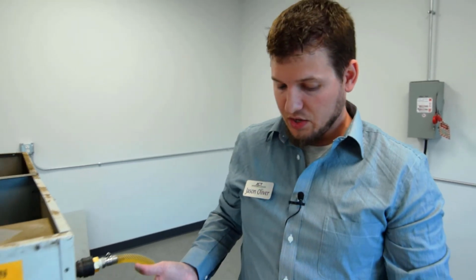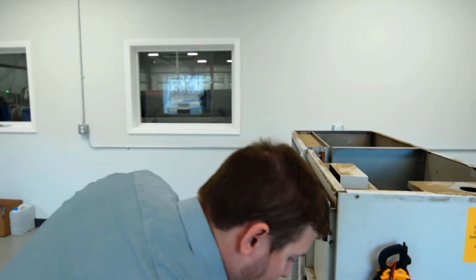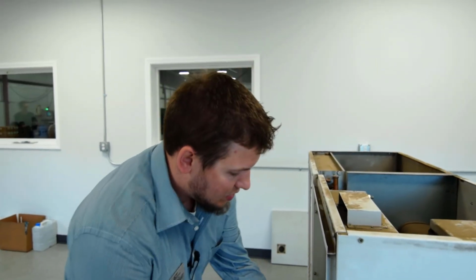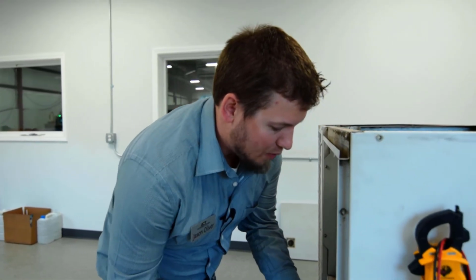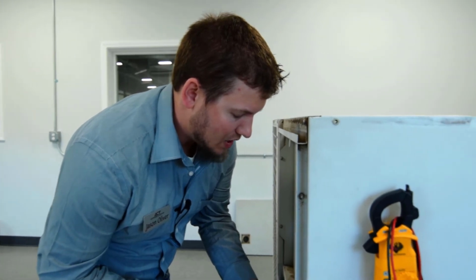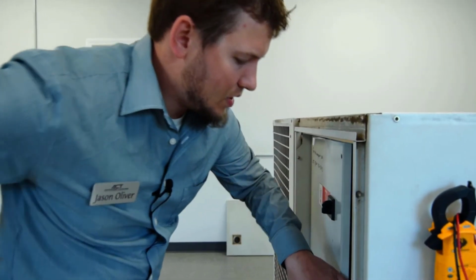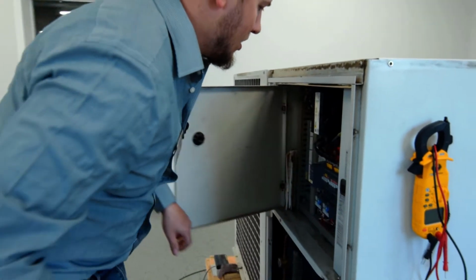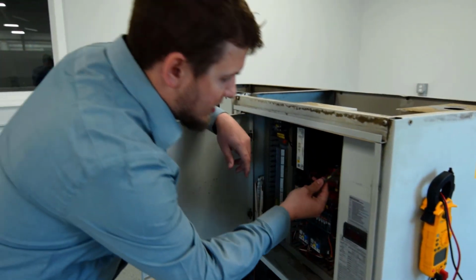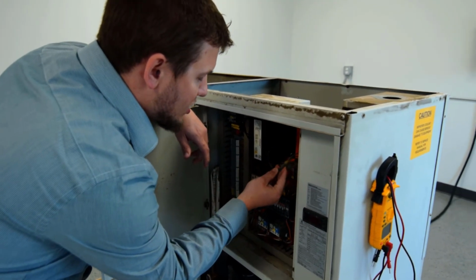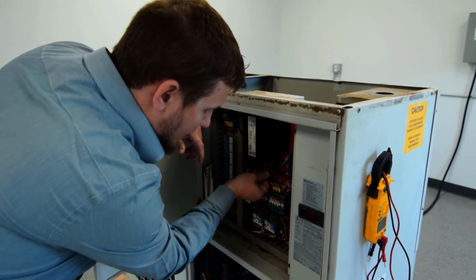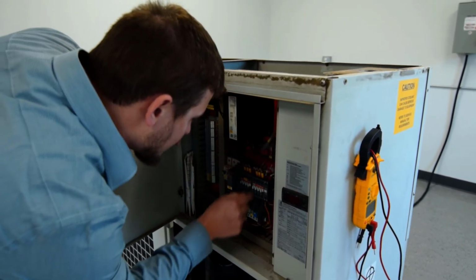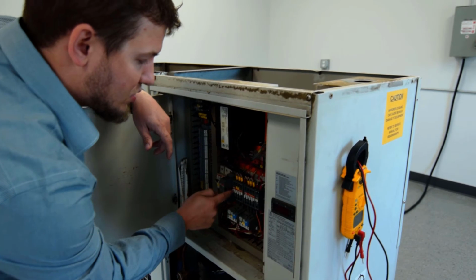Step number 5 on this checklist is to verify the electrical controls in the system. And the best way to do that is just to do a visual inspection of the wires. Make sure there's nothing frayed or no damages or melted plastic anywhere. It's important to verify with the power off that the insulation on the wires isn't damaged, that it's not brittle, that there are no wires sticking out, and that the contactors are not burnt.